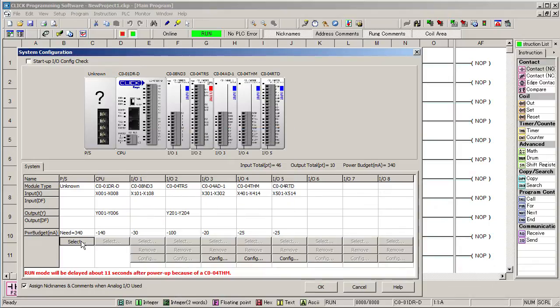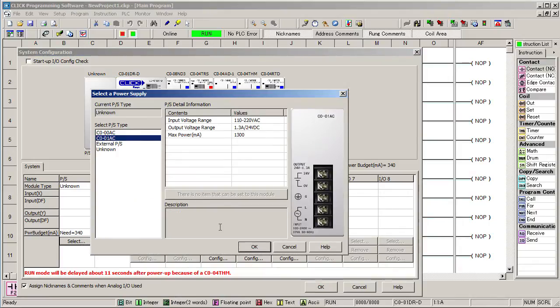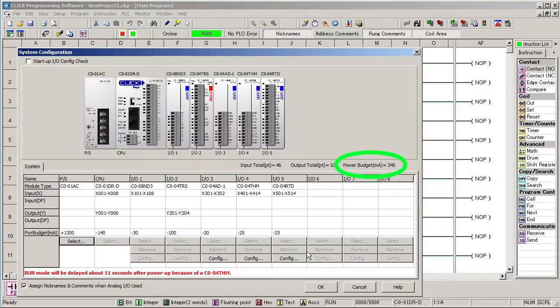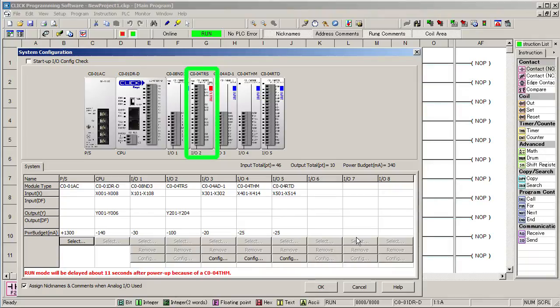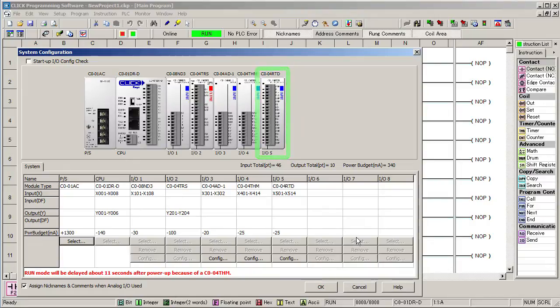We're using the AC supply so we select that. Now we can see how we're doing power budget wise. Let's see, we're only using 340 mA of the 1300 available, so we're in good shape. The software found an 8 input digital module, an 8 output digital module, a 4 input analog 4 to 20 mA card, a thermocouple module, and an RTD module. Perfect.